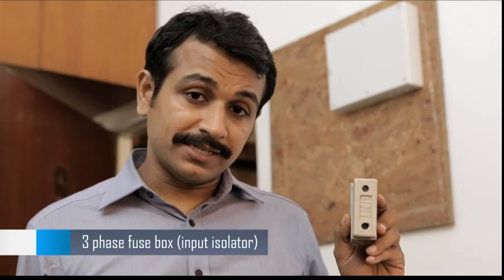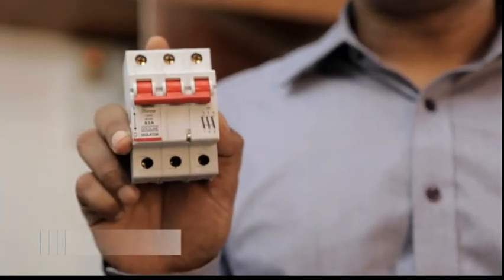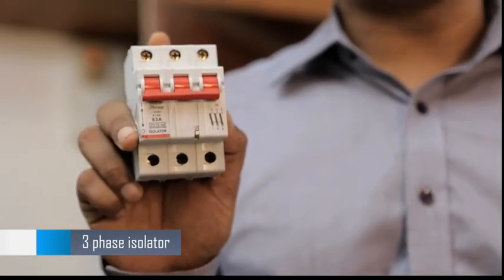Since the total load is greater than 3000 watts, the input supply should be 3-phase. Therefore, we need 3 single-phase fuses and 1 3-phase isolator that acts like a circuit breaker.